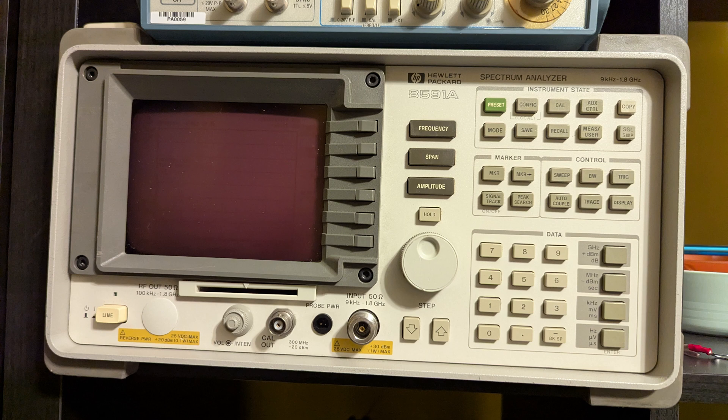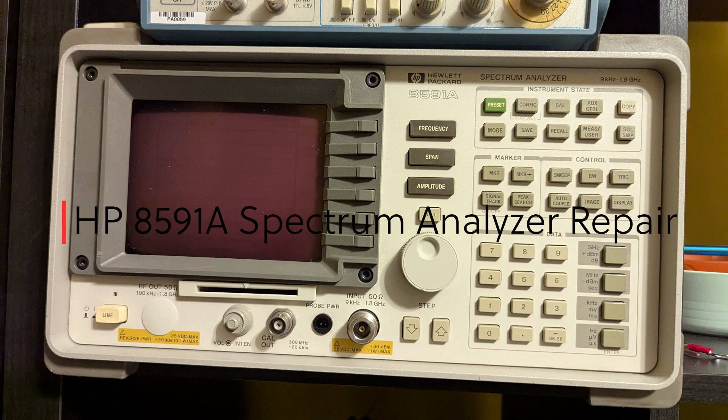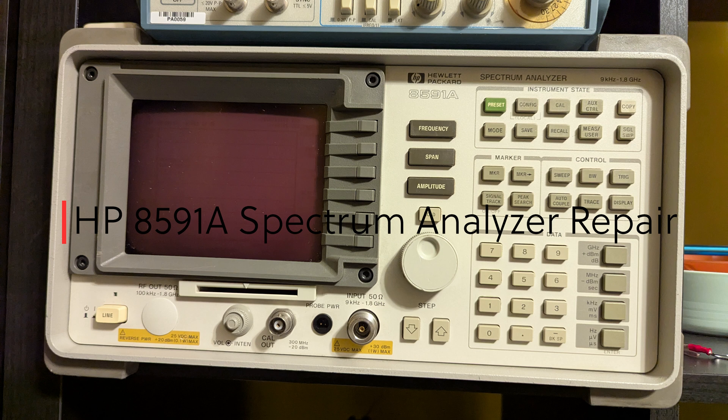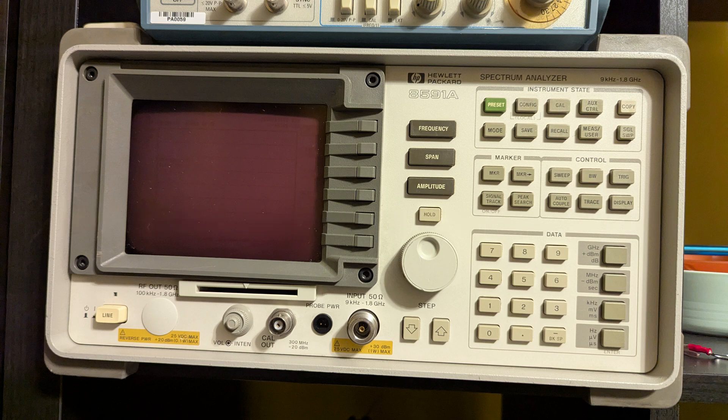I repaired an HP 8591A spectrum analyzer and had an odd problem I'd seen documented but hadn't seen an example of fixing. When it started up, it would run really slowly on screen updates, taking 30 seconds per update as though the CPU was busy, but it looked like it was working. Sadly, I didn't get a video of this.